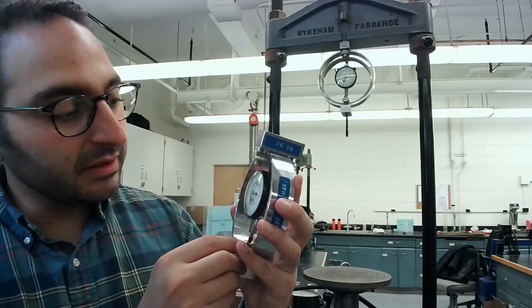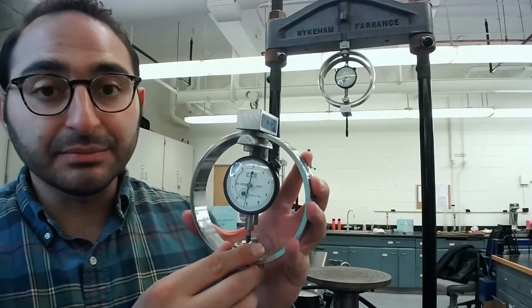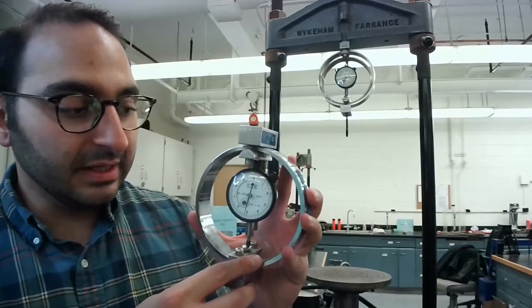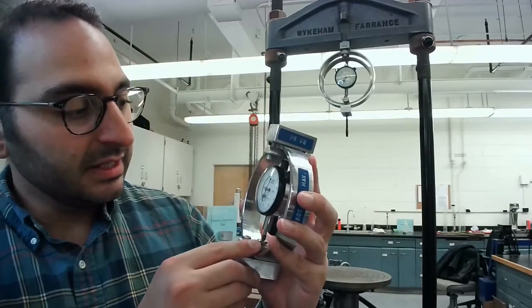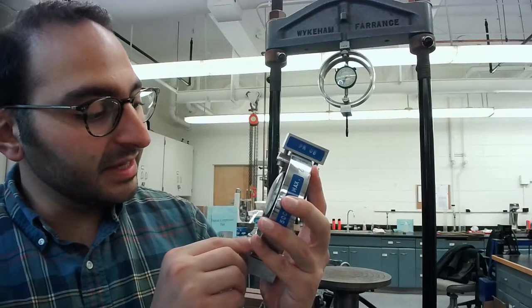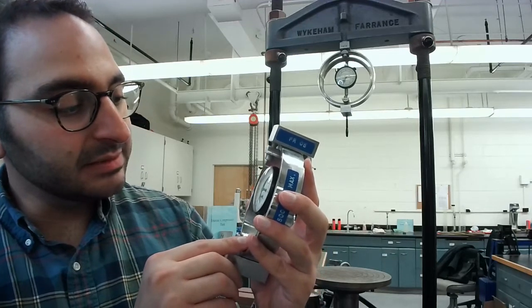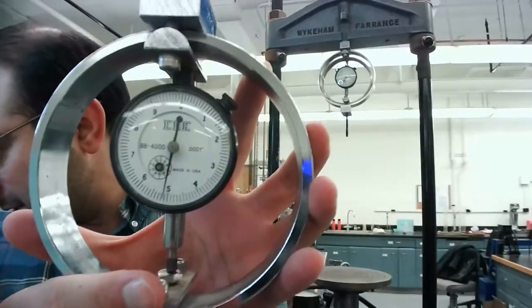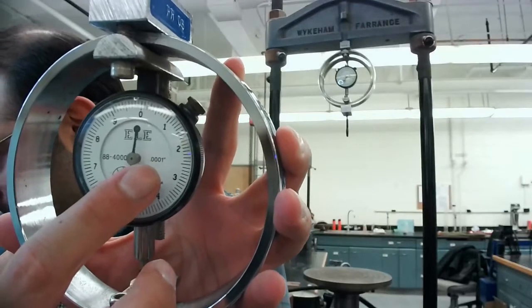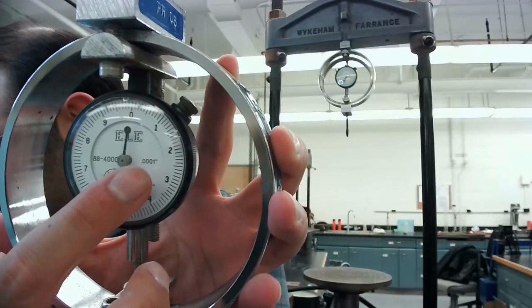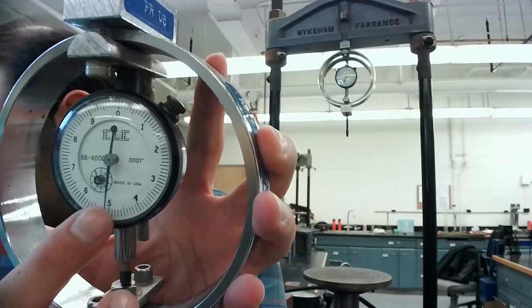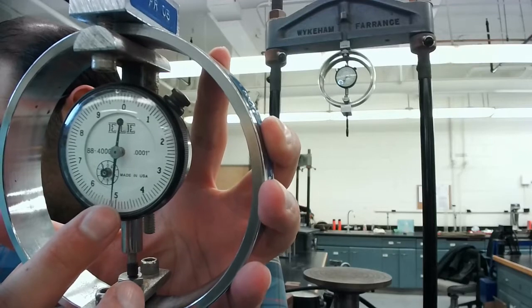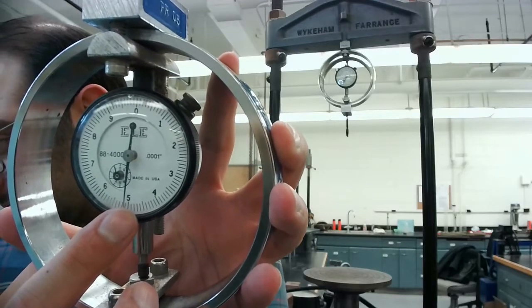Every tick mark on the load ring has a particular measurement. For example, this load ring, every single tick mark is measuring 0.0001 inches. I'll try to show this to you. That 0.0001 inches is what you'll be measuring as the tick goes from, for example, five to the next tick mark.